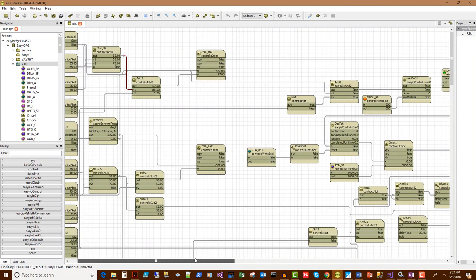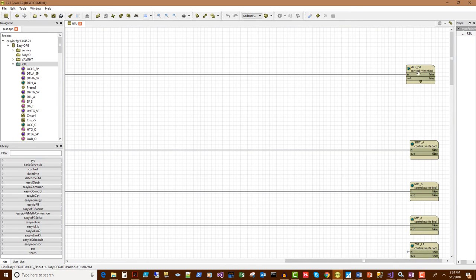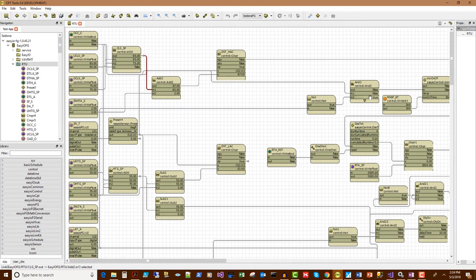Now, that being said, some manufacturers really separate their field controller and their supervisory device. EasyIO combines those together. Now, I'm not going to say whether one is better than the other. You all know by now I'm vendor agnostic. However, the fact that they combine this together allows me to create my alarms in the program and then reference those directly on my graphics. With other manufacturers, you would eliminate alarms here and you would do those in the supervisory device. No one way is necessarily better than the other. It's just knowing the software and the hardware that you're working with, and then building your programs accordingly.